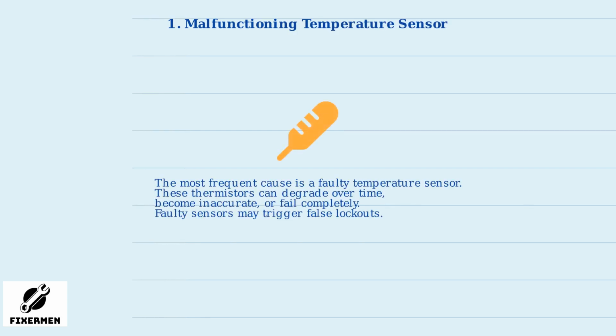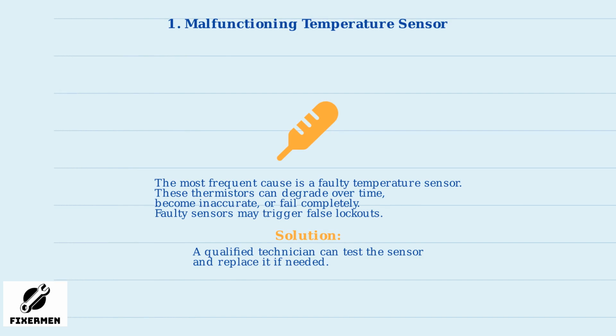Now let's examine the most common causes of Lennox Error Code 231 and their solutions. The most frequent cause of Error 231 is a malfunctioning temperature sensor. These thermistors, which monitor outdoor temperatures, can degrade over time due to exposure to elements, become inaccurate from dirt or corrosion, or fail completely. Lennox has even issued recalls for certain models with faulty sensors that contribute to false positives.